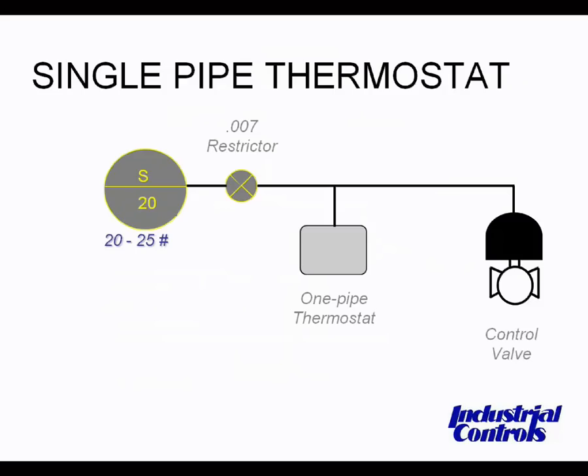We're going to go on to room thermostats now. The first one we'll talk about is the single-pipe thermostat. Note there is only one piping connection to the thermostat, and a 0.007-inch orifice is installed in the main air supply feeding the thermostat and the controlled device. The restrictor is placed in the airline because the inlet air to the low-volume controller must be of a smaller volume than can be bled off by the controller's nozzle. If no restrictor were in the line, the control device would immediately go to full stroke and would be stuck there.